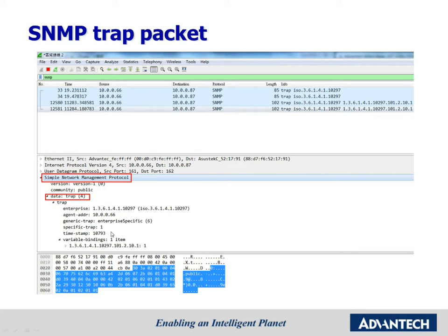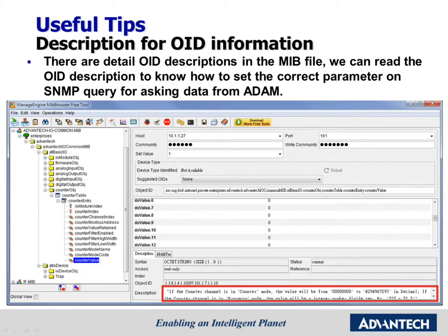You may have a question: what is the timestamp here and what is its role? Please note that this timestamp is the time elapsed since the module was powered on, and it is in units of 10 milliseconds. In this slide, we will share some useful tips. Users can follow the OID description to analyze the query data or send the correct parameters to ADAM. For example, if a channel of ADAM is set to counter mode, the SNMP query data the user gets is exactly equal to the counting numbers they want to know.